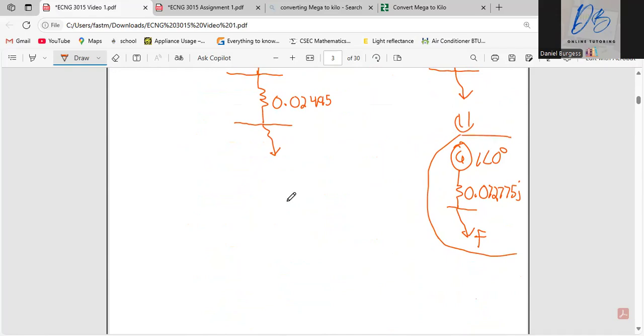And with that, the next thing I will ask you to get is something called a short circuit current or a fault current. And I short circuit will be 1 on Z per unit. So in this case, it will be 1 on 0.027775j.